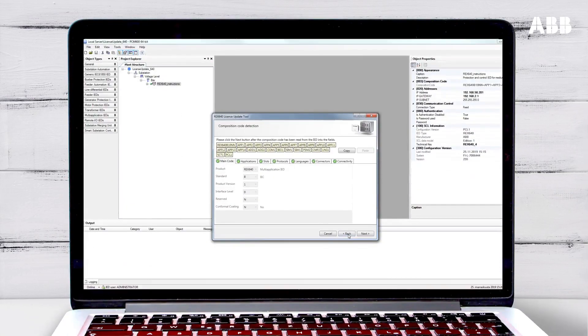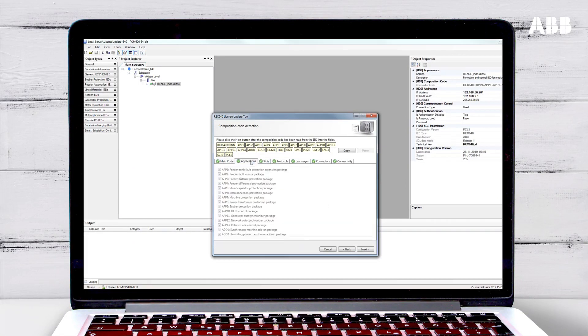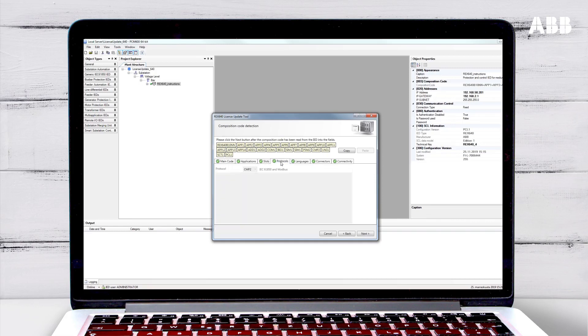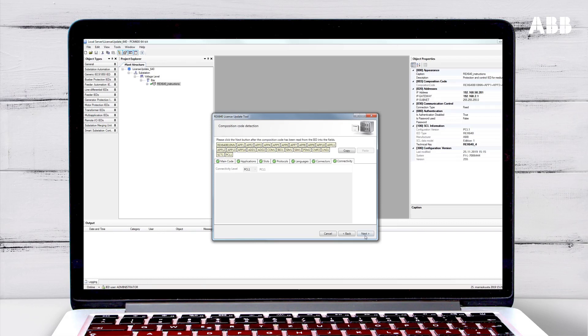Here you can see the composition code. The code references all of the applications, which are the software packages and slots, or hardware, that are enabled on the relay. In Online mode, this information is automatically gathered from the relay. In Offline mode, you will need to enter the composition code by selecting the correct options in each of the tabs.